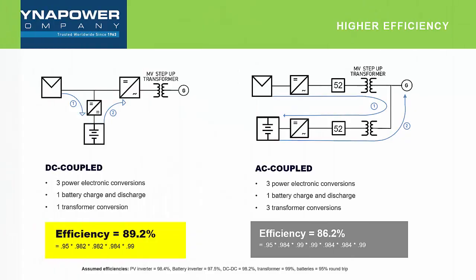Now, on the efficiency side, again, there are advantages with a higher efficiency on the DC coupled system. If we look at the diagram on the left, the round trip efficiency is a cycle whereby you enter the storage system through the DC converter, and then when you discharge, you go out through the DC converter again, and then out through the PV inverter. And then before you get to the grid, you go out through the medium voltage step-up transformer as well. Now, if we take a look at the diagram on the right, the AC coupled configuration, to charge the batteries, we go out through the PV inverter, up to medium voltage, step back down to low voltage on the storage side, and then are rectified through the storage inverter to charge the batteries.